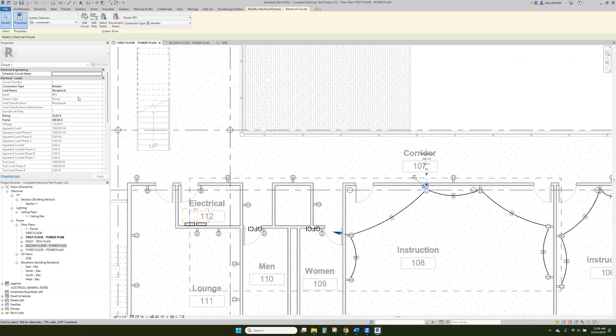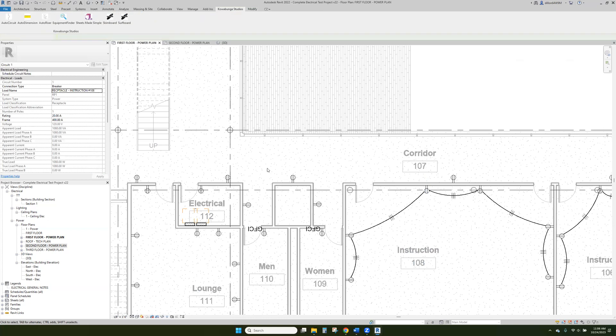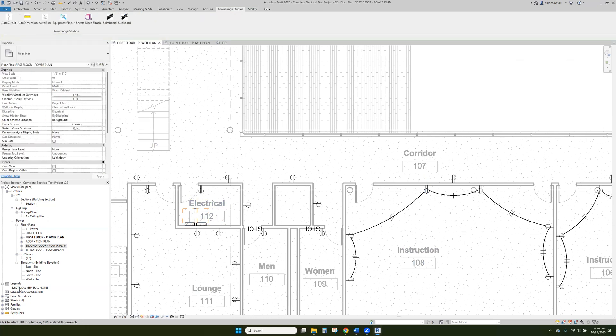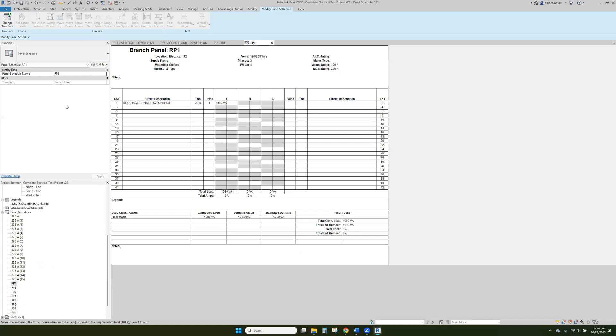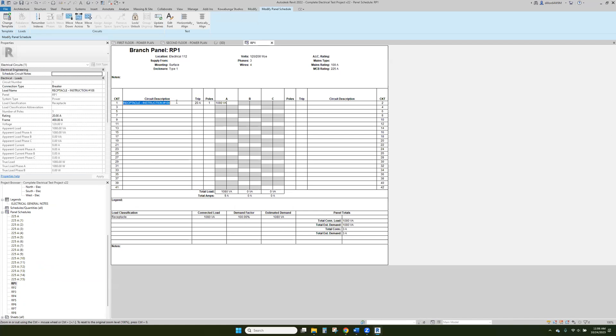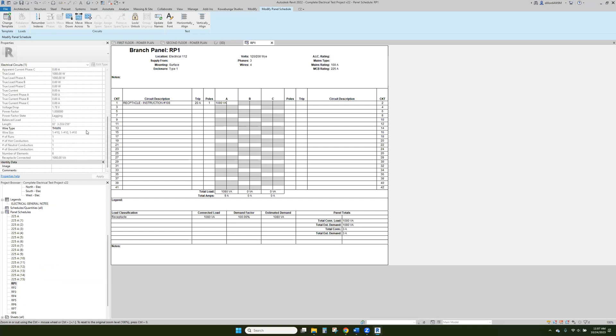And then the next thing that we can do in here, so we just have a load name is receptacle. So we can say receptacle-instruction room instruction number 108. And we can capitalize this. So then when we look on our panel schedules and we go to RP1, we can see here that we have receptacle-instruction 108. And anything that we change here will change back in that form as well. Everything's connected all the way through.